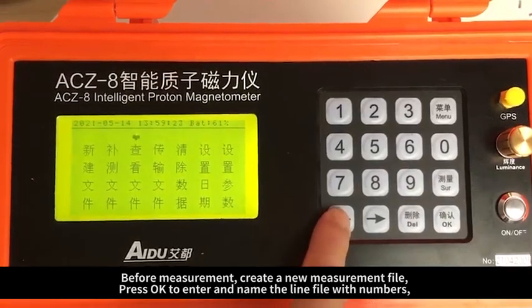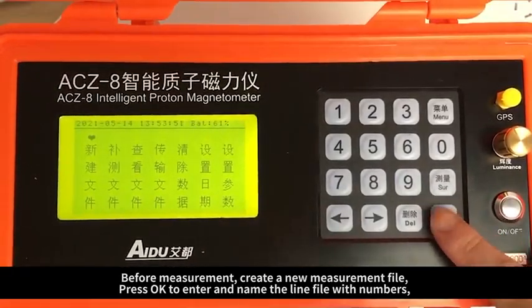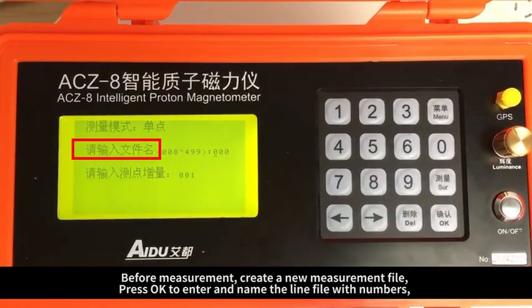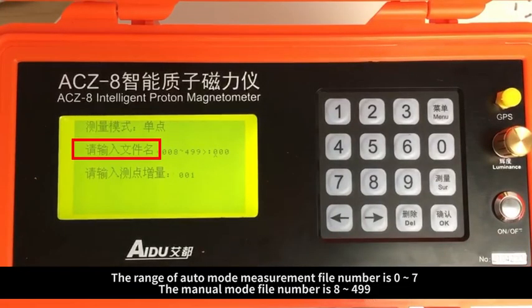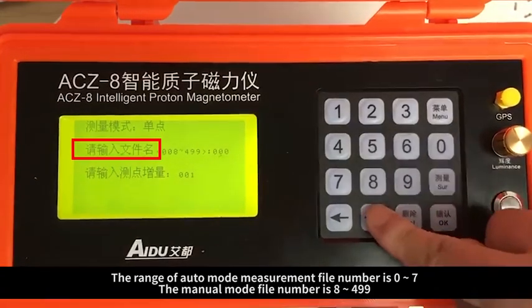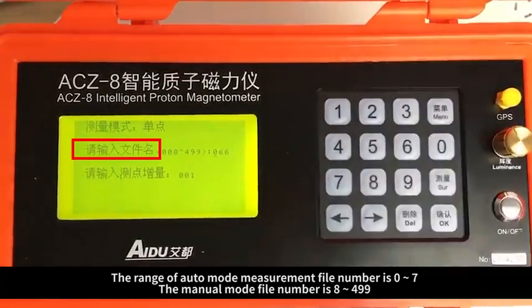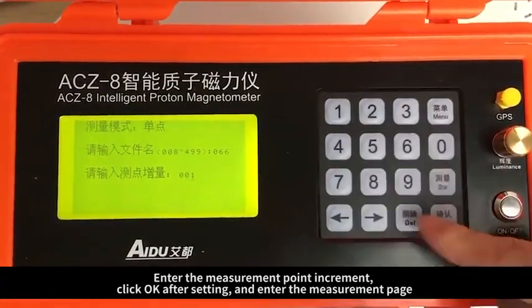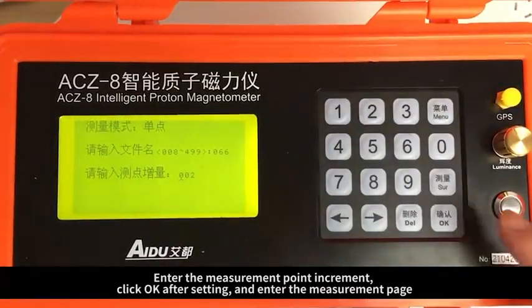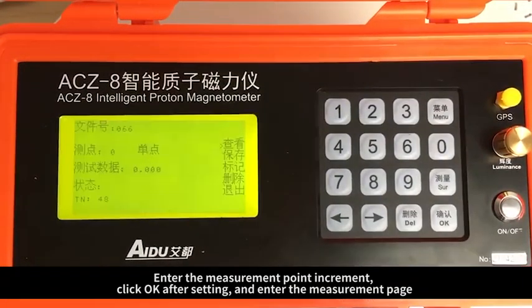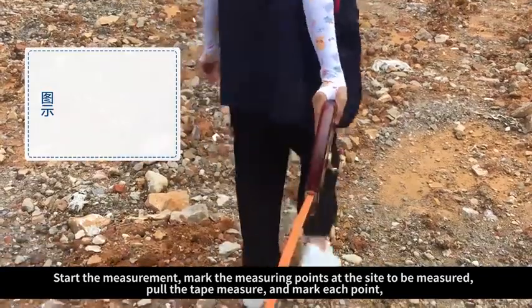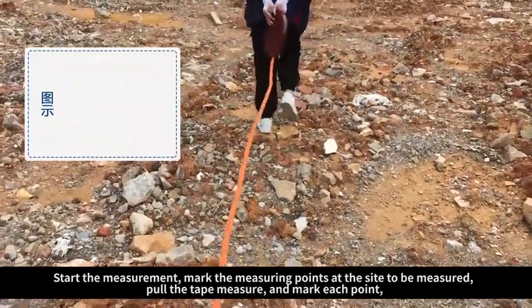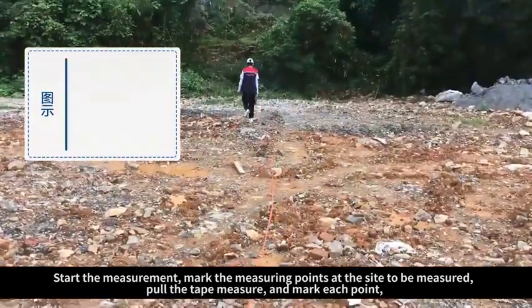Before measurement, create a new measurement file. Press OK to enter and name the line file with numbers. The range of auto mode measurement file number is 0 to 7. The manual mode file number is 8 to 499. Enter the measurement point increment. Click OK after setting, and enter the measurement page. Start the measurement, mark the measuring points at the site to be measured.